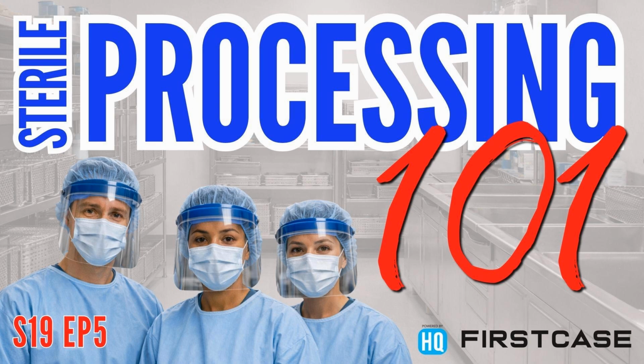So those low temp options are typically a hydrogen peroxide sterilizer or an ethylene oxide sterilizer. Most hospitals these days are using hydrogen peroxide. Back in the 80s and 90s, OSHA put out some scary information about ethylene oxide causing cancer in humans, so the market moved pretty quickly towards hydrogen peroxide. But there are still some EtO, ethylene oxide sterilizers out there, and there are safe ways to operate those. So those are the main ones between steam and low temp options.